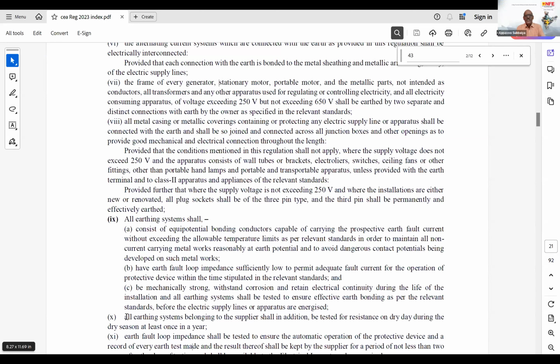So, in simple words, for LV installation you adopt the TN-S system and earth loop impedance as per regulation. And if it comes to the HT installation, you address the issue of step and touch potential and current division, everything. Then go for earth resistance. It's not only the earth electrode. It depends on the earth mat. There are so many things available.